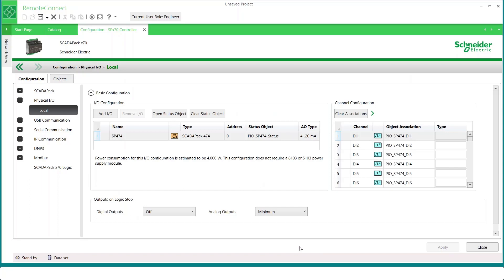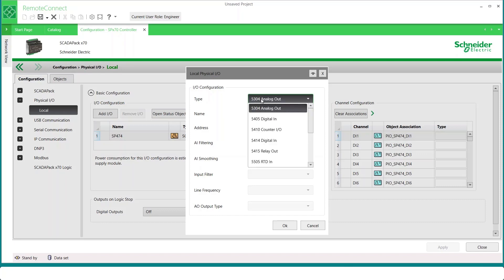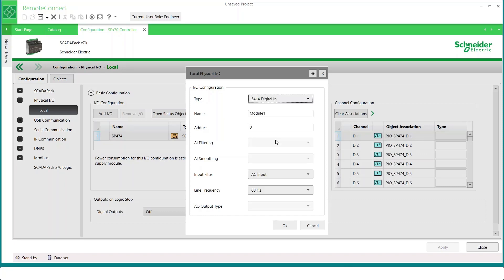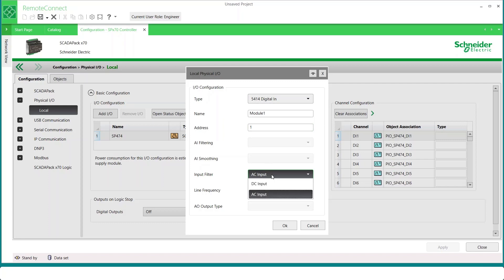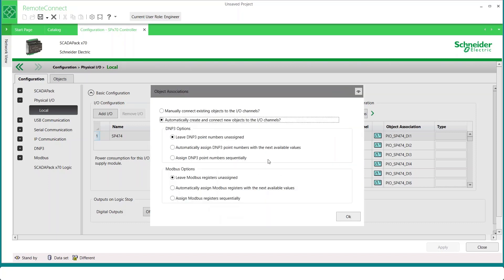Other physical I/O devices can be added here by clicking the Add I/O button. In this case, I'll add the 5414 digital input module. You can see here that we can change its name and the module address. We can edit other parameters such as the input filtering and the line frequency. In the next step, you can choose to allow Remote Connect to automatically create objects with default names for each I/O point. Or choose to manually configure these later. Here, I'll select Automatically Create.